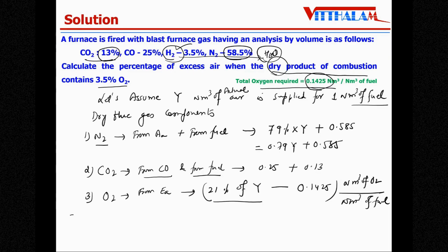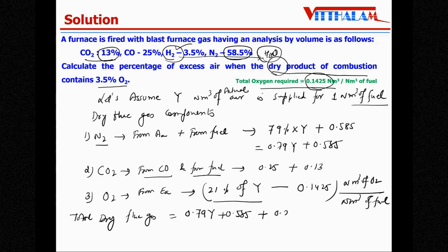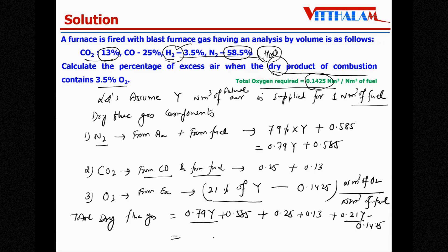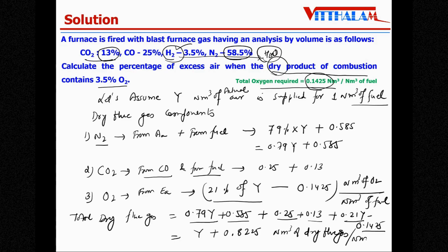Now total dry flue gas = (0.79y + 0.585) + (0.25 + 0.13) + (0.21y − 0.1425). Simplifying: 0.79y + 0.21y = y, and 0.585 + 0.25 + 0.13 − 0.1425 = 0.8225. Therefore total dry flue gas = y + 0.8225 nm³ per nm³ of fuel.